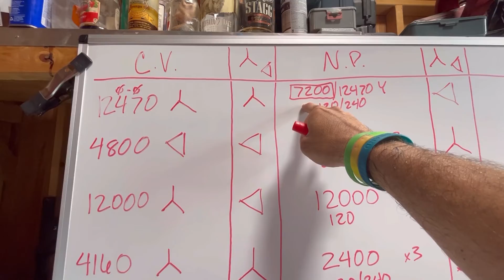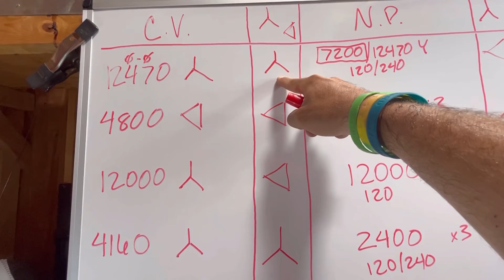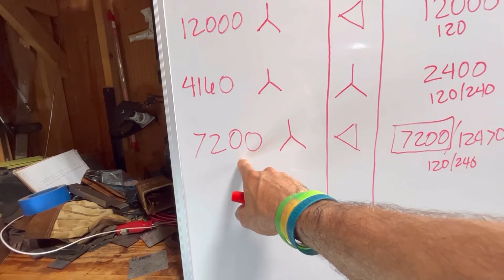See up here, same transformer, different circuit. On this circuit, this transformer had to be hooked up Y because of where 7200 volts was on this circuit. On this circuit down here, 7200 volts lives phase to phase, right? Therefore, it has to be hooked up delta. Customer needs 120/240. We're just going to do that one again. 120/240, 3-phase 4-wire. So remember, customer needs determines secondary hookup. So delta divide, 120 goes evenly into 240. Answer is yes. Can I fulfill my customer needs with those transformers? If the answer is yes, fill it in.